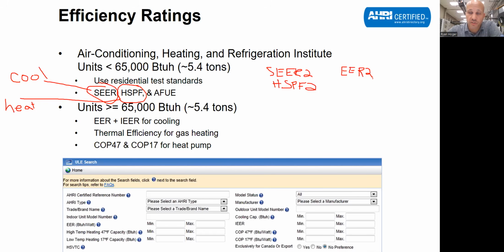That's the full load efficiency. It tells you how efficient this thing's going to be if you ran at maximum capacity and locked it in and let it roll there. That's not a real life scenario, so hardly anybody pays attention to that anymore. But it used to be the only metric we had. Now that we have things like SEER in the past 30, 40 years and HSPF2, we don't really care about EER, but it's there for old people. By old people, I don't mean old customers. I mean old people that make these rules. All right, so those guys are for how I test my cooling and my heating on these smaller systems.